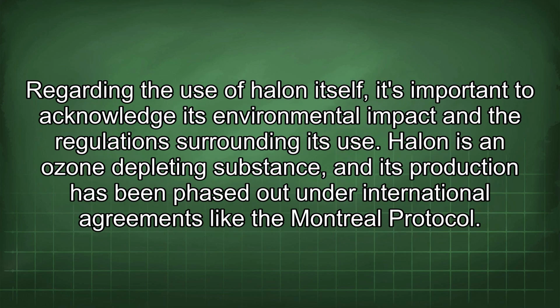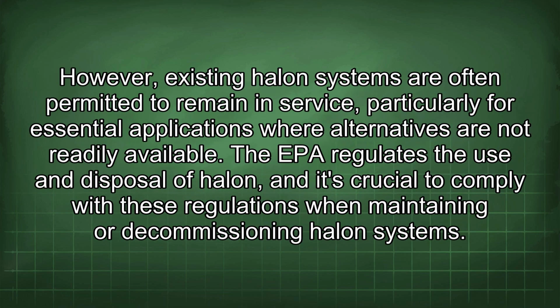Regarding the use of Halon itself, it's important to acknowledge its environmental impact and the regulations surrounding its use. Halon is an ozone-depleting substance, and its production has been phased out under international agreements like the Montreal Protocol. However, existing Halon systems are often permitted to remain in service, particularly for essential applications where alternatives are not readily available. The EPA regulates the use and disposal of halon, and it's crucial to comply with these regulations when maintaining or decommissioning halon systems.